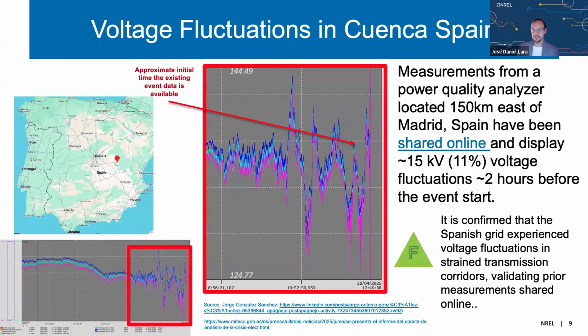Now, one interesting piece that was discussed is that even though the blackout happened around noontime, heavy fluctuations of voltage were observed in the Spanish system. This is a screenshot from a power quality measurement taken at a wind power plant in this location in Spain, showing voltage fluctuations of up to 11%, even two hours before the event started. Originally this was one of the speculations being tossed around.